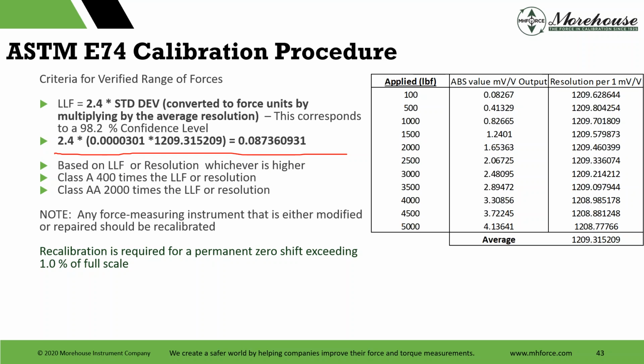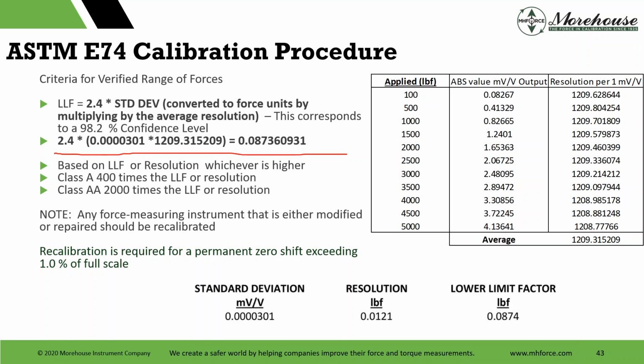So say you overload the load cell. If you shifted the zero by more than 1%, you probably damaged the cell. You could have it recalibrated, but if you have a zero shift at that 1%, you're going to have additional error. Anytime you shift the zero, you're going to have additional error. So if you overload it, it should be recalibrated, even if it's below the 1%, because there's still additional error. The output can change depending on how low you need that uncertainty, because if it is overloaded and you go with it for a year of data, you could be issuing some recalls, depending on what you're claiming.